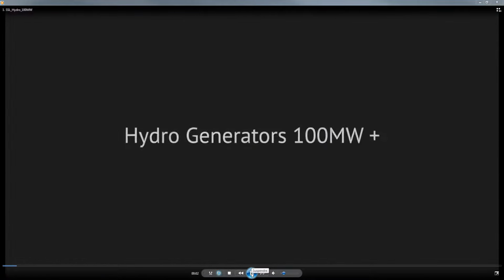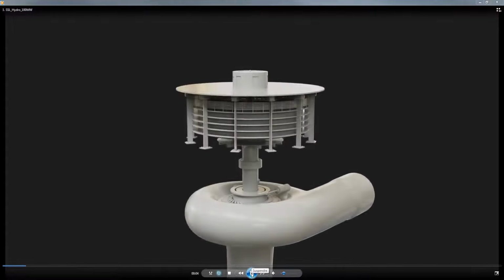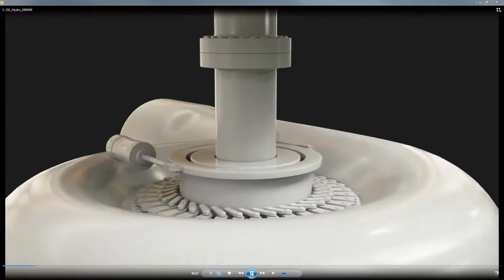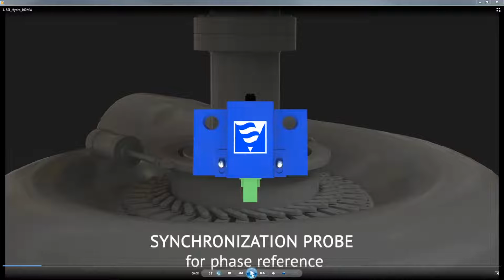Okay, so this is basically a system we recommend for generators that have 100 megawatts or more. Now, the first thing we do is kind of strange, but we specify a synchronization probe, which is probably the smallest piece of equipment in the system.